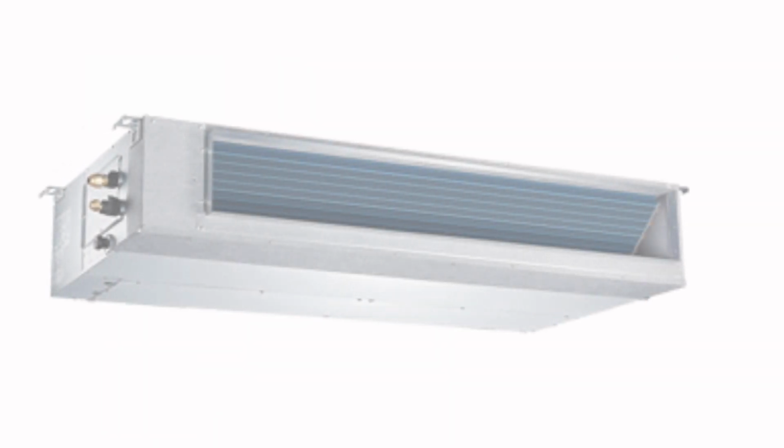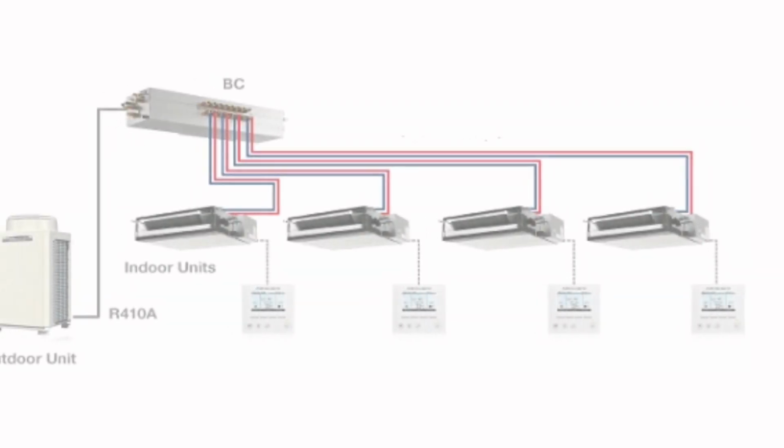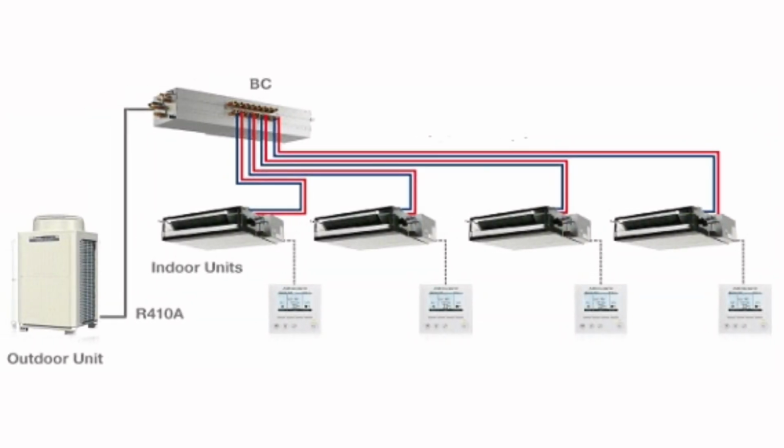They are used in some office buildings and shopping centers, and typically specified where there are multiple small spaces requiring individual control. Typically, an individual FCU serves only up to 150 meters squared, so there can be tens or even hundreds in a building. FCUs are, however, most commonly used as a supplement to a building, for which other HVAC systems provide the majority of the air conditioning.